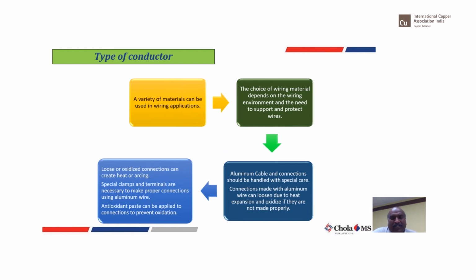Of course, for aluminum cable, it also depends upon where you want to lay and use these cables. If it is a more saline area, then you might need to look for a cable suitable for that. For example, if you have a building and next to that building you have acid tanks and transfer pumps, then please be clear on what type of cables you are using, or ensure that the proper insulation and sleeves are provided. If it is close to the sea, you might have too much sulfation taking place. So aluminum cables and connectors should be handled with special care. A connection made with aluminum wire can loosen in due course because of oxidation. So use the right lugs and lug paste.